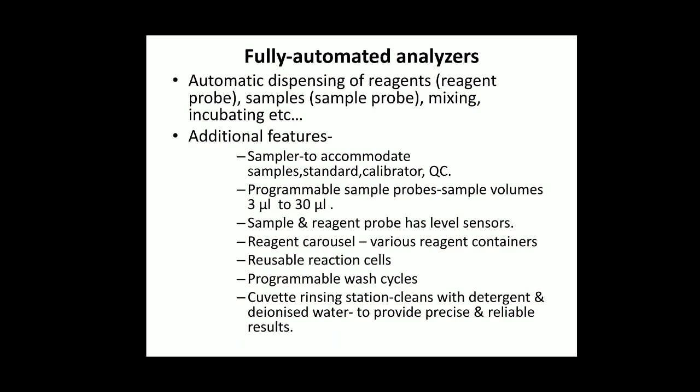In the fully auto analyzer, automatic dispensing of reagent, sample, and mixing is done. The sampler accommodates samples along with standard calibrators and QC samples. Sample volume is 3 to 30 microliters. A main feature is sensors — both for sample and reagent. If the sample or reagent quantity is below a certain level, a beep sound alerts us to check and refill the sample or reagent.